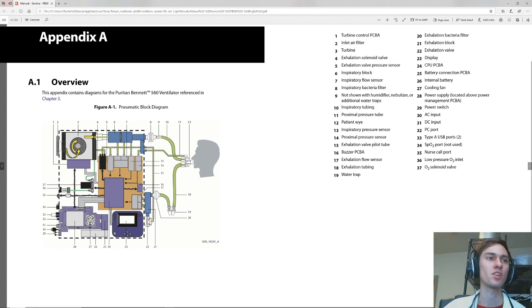17 is the exhalation flow sensor. Okay, we got that. Yep, we decided on that already. That's cool. 36, low pressure O2 inlet. Yeah, we had that. And then 37 is the O2 solenoid valve, which we also found. Okay, cool. So I think we reverse engineered everything on the main unit. So this was a super good find.